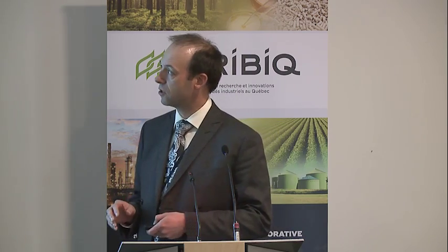Now, when this equipment is shipped to your future plant, you can ask for the installation qualification. The installation qualification is meant to demonstrate that the installation at your site is done as prescribed. So we prepare some specifications for the installation: what is the requirement in water, in steam, and how it should be connected. This is the installation qualification.